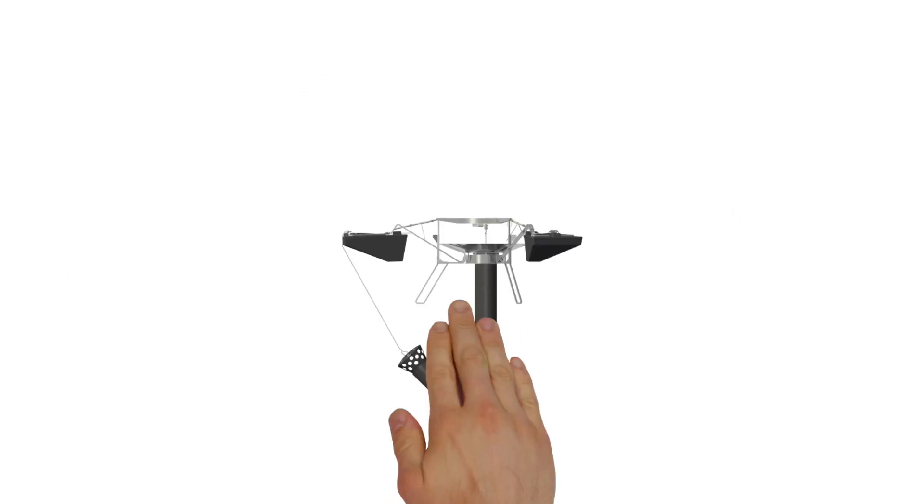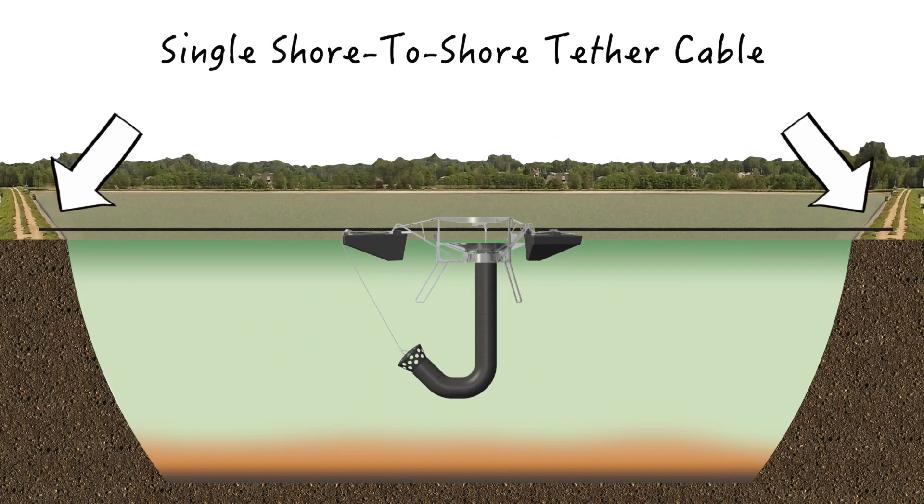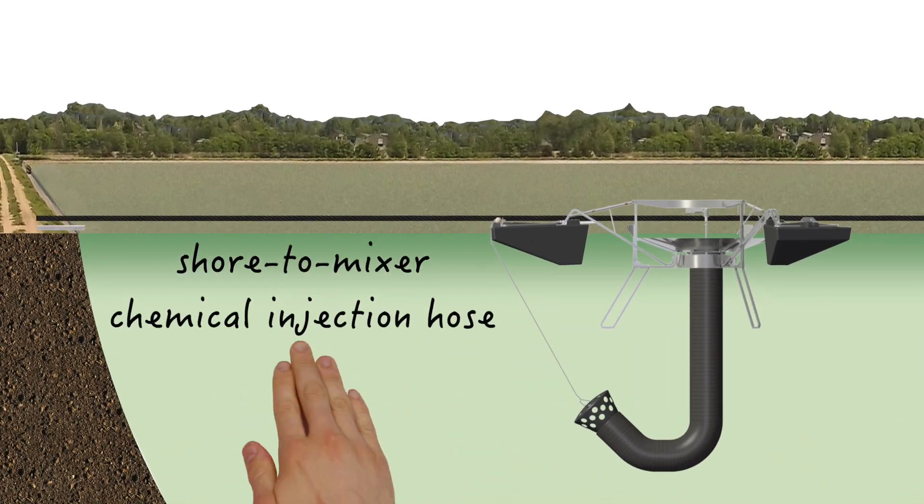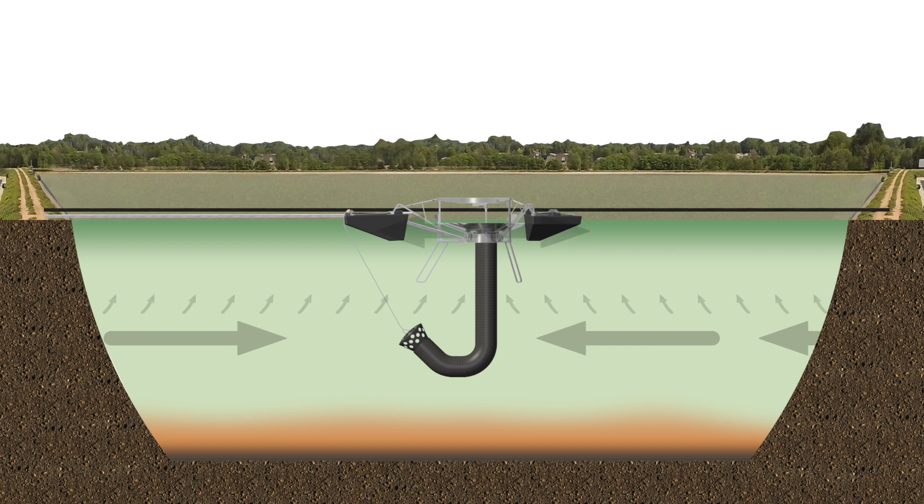And it all starts with a floating wastewater mixer. The mixer is anchored using a single shore-to-shore tether cable, which is able to span most lagoon dimensions. Once tethered, an injection hose is run from shore to the machine, fastened along the tether cable, terminating just below the machine impeller. And just like that, Medora's floating wastewater mixer is now ready to receive and distribute the phosphorus precipitant of your choice.